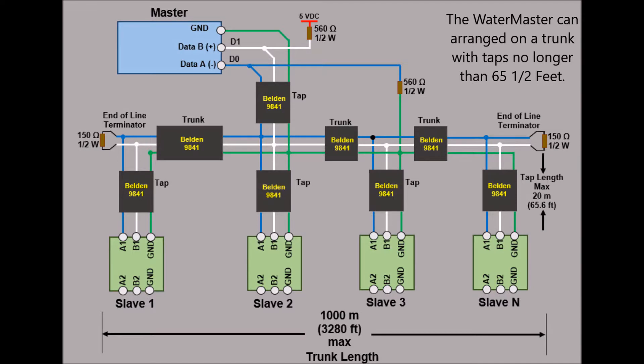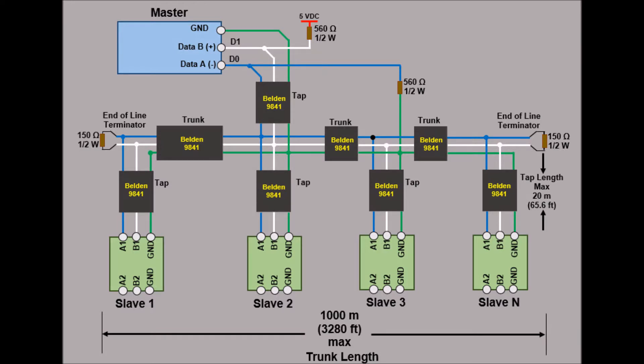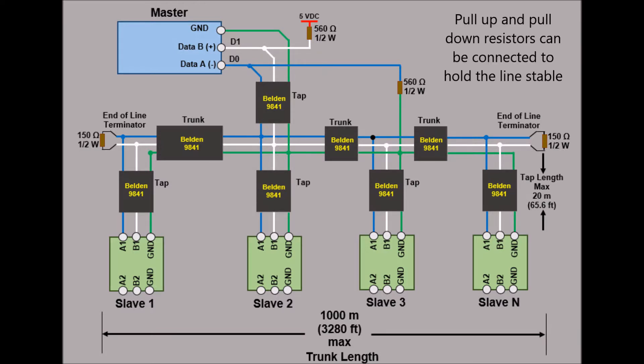The Watermaster can be arranged on a trunk with taps no longer than 65.6 feet. When there is no data activity on an RS-485 balanced pair, the lines are not driven and are thus susceptible to external noise or interference. To ensure that the receiver stays in a constant state when no data signal is present, the signal lines need to be biased from a single point on the bus at or close to the master.